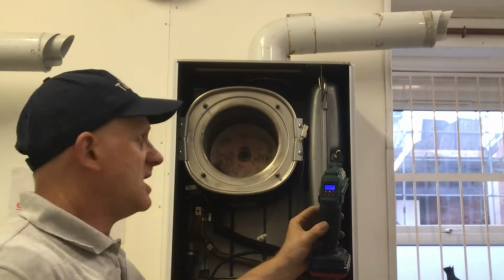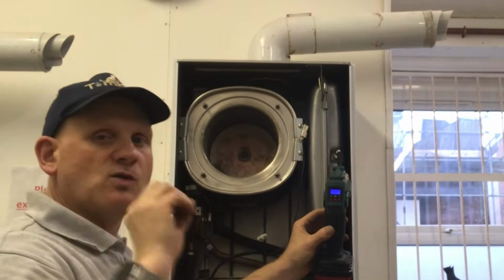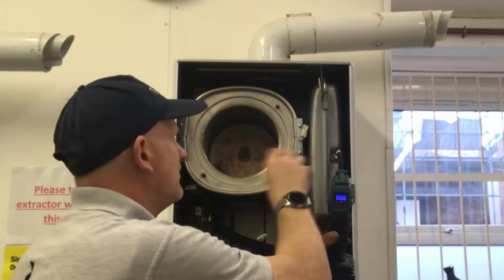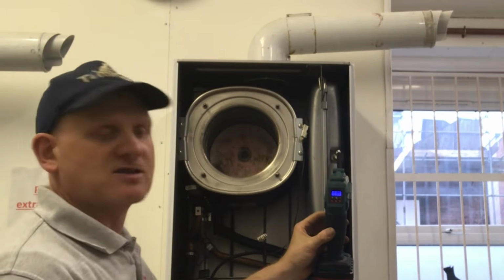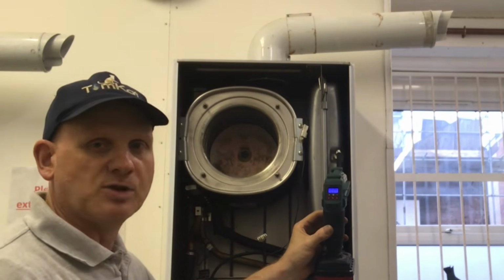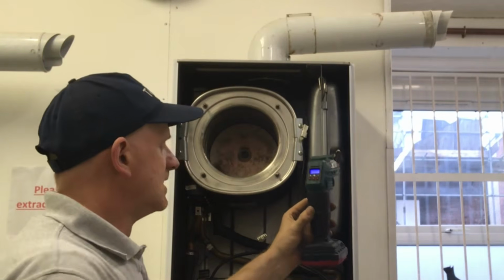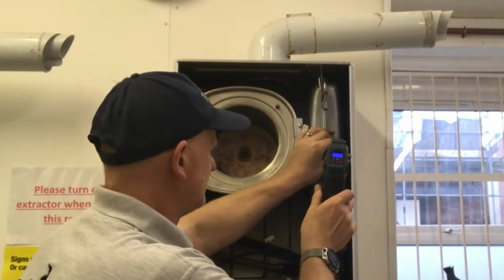If you put too much air in, the water can't compress it, and if you put too little air in, then the expansion will be taken up inside the boiler and blow off on the pressure relief valve. Now, I'm going to be quick getting it off.